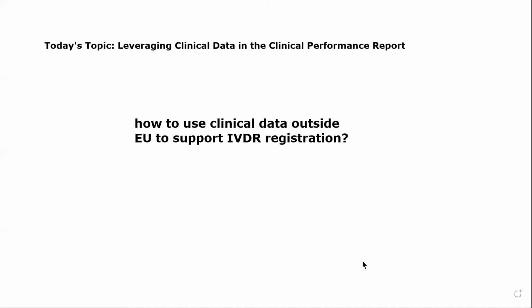The critical part to include here is to make sure that you're clearly documenting the source of each of the clinical data sets, and that you're still subjecting them to the same appraisal and directly explaining any potential limitations with those clinical data sets. So it's not to say that you can't or shouldn't use those global data sets if available, but the explanations and the documentation of the sourcing of the clinical data sets is going to be what the notified bodies are going to be looking for.